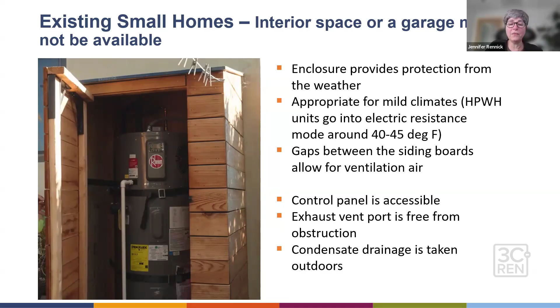Keep things quiet. Now, the one thing, architects and energy consultants, on your Title 24 CF1R, if you do something like this, you need to make sure that yes, you're probably using a NEEA rated heat pump water heater, but take a look at the table that deals with the heat pump water heater specifically and look at the tank location and the ducted air source or ducted outside air source. It's not always ducted, but if you do an installation like this in an exterior closet that meets all the net free ventilation requirements, etc., then those should all say outside.